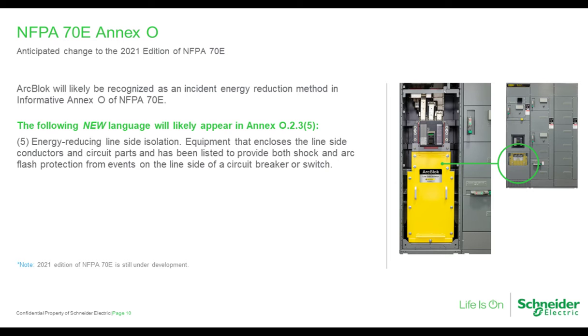Okay, so the previous slide was from the NEC, the National Electrical Code, and we know that the NEC covers installation requirements. Another standard that's widely used in industry is NFPA 70E. And 70E is the standard for electrical safety in the workplace. NFPA 70E does not cover installation requirements. Instead, it provides information to help protect employees. Following 70E helps employers comply with federal regulations such as OSHA 1910 and 1926.